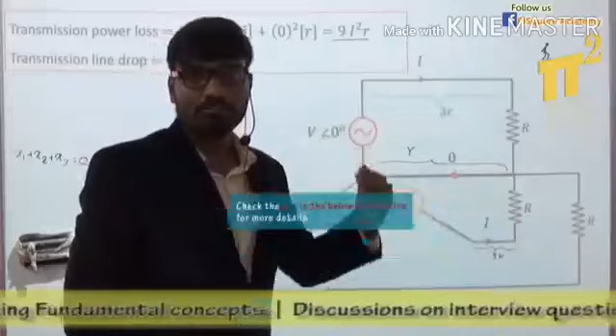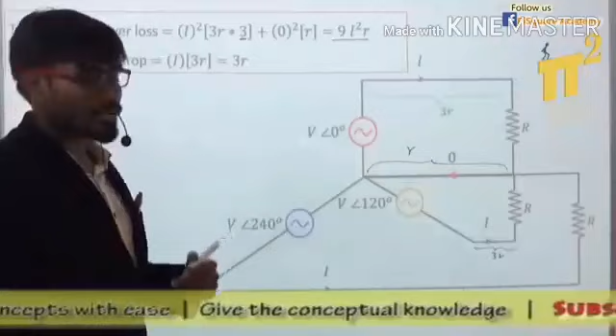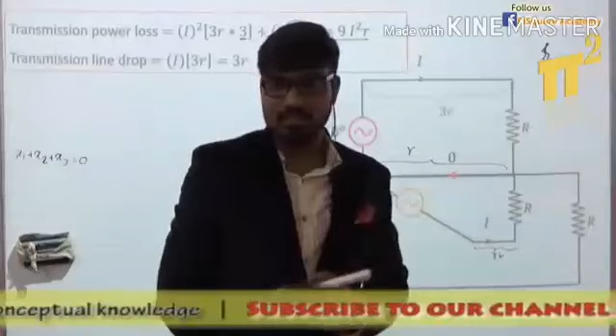Also here, for the transmission line voltage drop, taking this phase, the return conductor is not offering any voltage drop, only the phase conductor is offering a voltage drop, which is 50% less than earlier. In the earlier case we got 6R, here we got 3R. I hope now the second case also is clear.